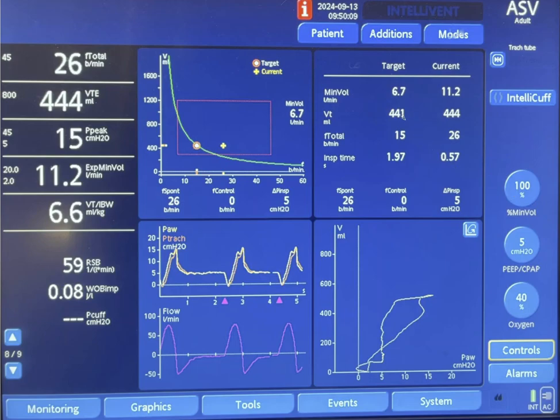Then the machine will take the ideal body weight for the patient which is 67 kg and multiply that by 100 ml and that will give you a targeted minute ventilation of 6.7 liters.